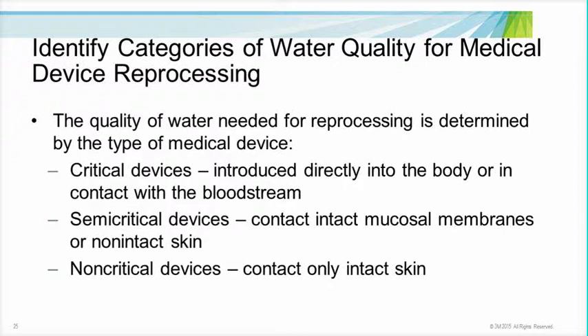The type of medical device that will be reprocessed determines the quality of water that should be used. Medical devices are placed into one of three categories determined on the potential risk of infection associated with the intended use. These are referred to as the Spalding Classification and are described in the document from the Centers for Disease Control and Prevention and the Healthcare Infection Control Practices Advisory Committee, and the document is entitled Guidelines for Disinfection and Sterilization in Healthcare Facilities. This document was published in 2008.